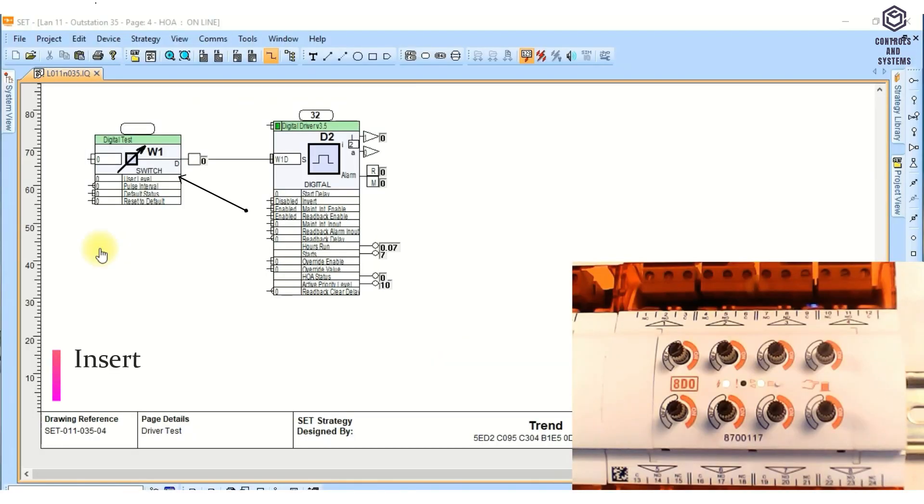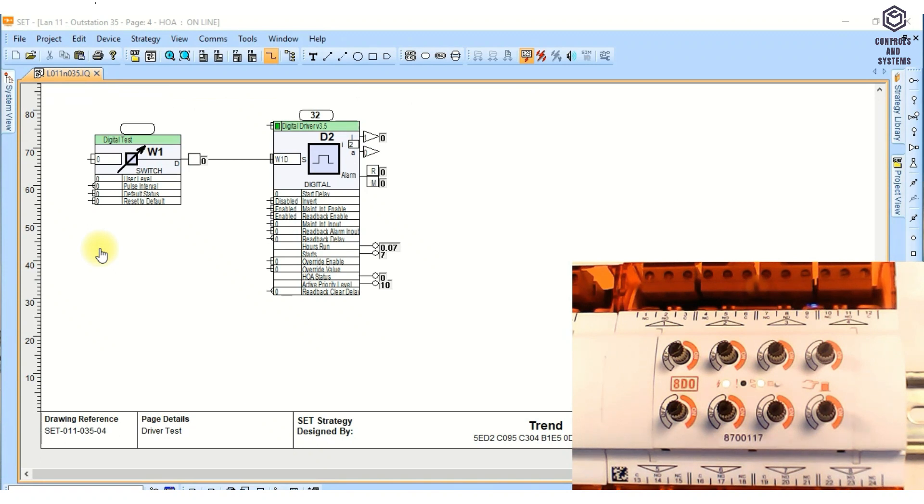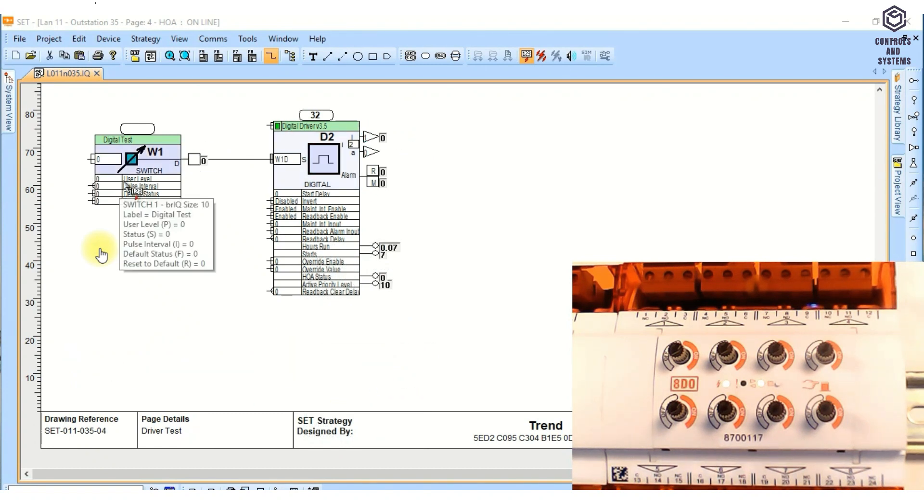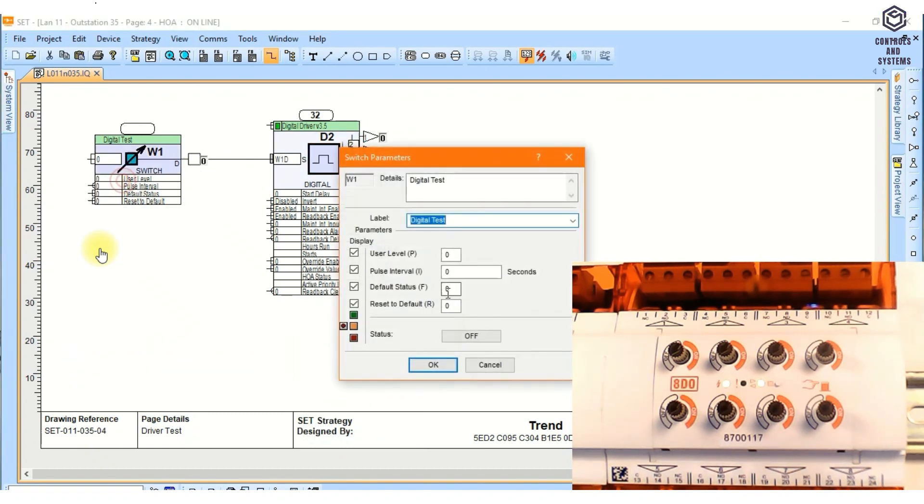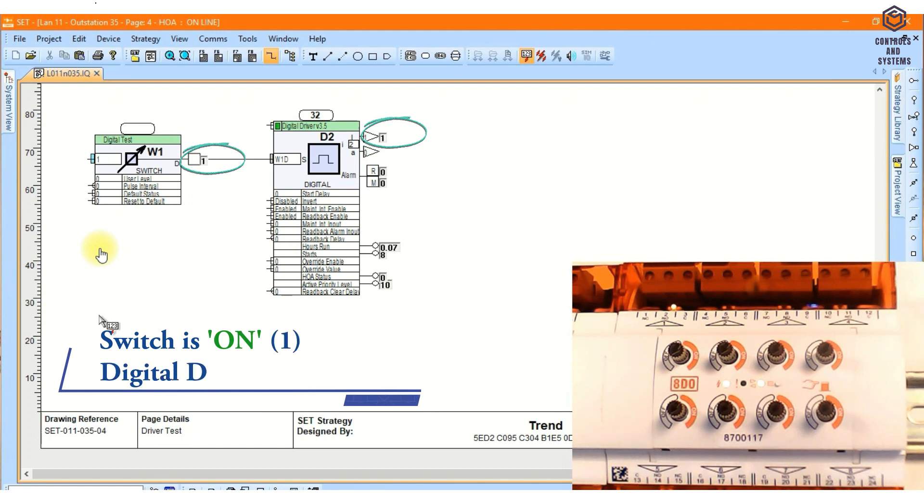Simulation. Insert the switch block and digital driver block into the page. Now it is in auto mode, so the input status is off and the output status is off. Double click the switch block, change the switch status from off to on, click OK, so now the input status is on and the output status is on.